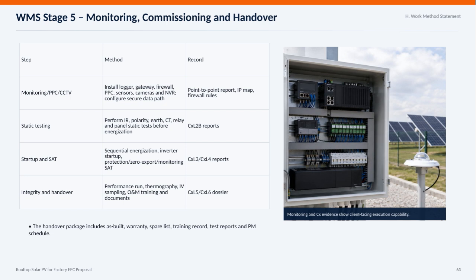Next, we conduct comprehensive static testing, including infrared, polarity, earth, current transformer, relay, and panel testing, all completed before energization to guarantee system integrity. The results are documented in CXL-2B reports. During startup and system acceptance testing, we perform sequential energization and inverter startup, followed by protection settings, zero export, and monitoring tests, producing CXL-3 and CXL-4 reports.